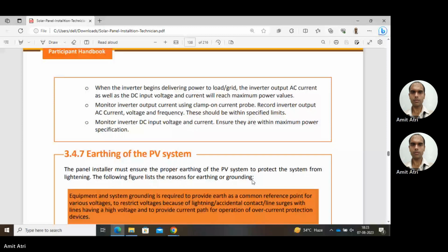The inverter AC current output, that is the output current, that is AC. That is the function of the inverter, DC to AC conversion. Okay, as well as the DC input voltage. Okay, so the input is DC, output is AC. So the input DC voltage and current will reach maximum power values. Okay, so when we have started the inverter, correspondingly the voltage at input, current at input, current at output, they will reach the maximum value. So we have to monitor the inverter output current using a clamp-on current probe that we've seen in the tools which we require for this installation process. So record inverter output AC current, voltage and frequency. We should make sure that they are within the specified limit.